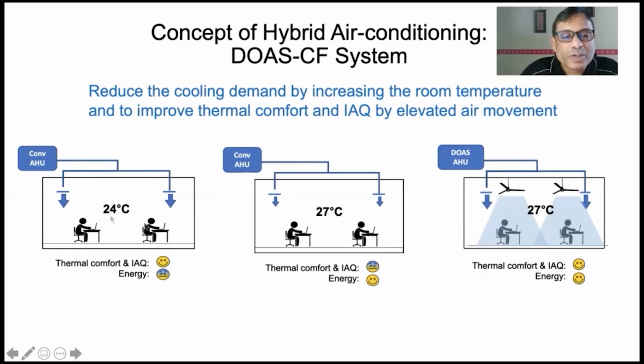Conventional system at 24 degrees Celsius: comfort and air quality are probably pretty good, but energy use is high, as we all appreciate. The same conventional system, if you increase the temperature to 27 degrees, thermal comfort and air quality could become a problem. With the dedicated outdoor air system - part of the hybrid air conditioning concept - we provide the space at a temperature of 27 degrees Celsius.